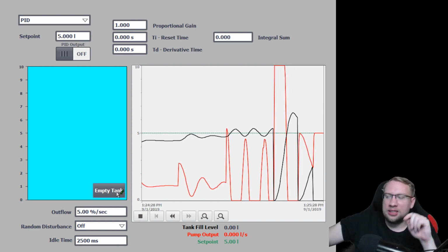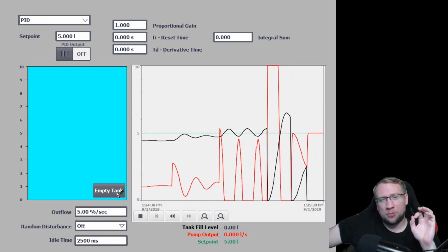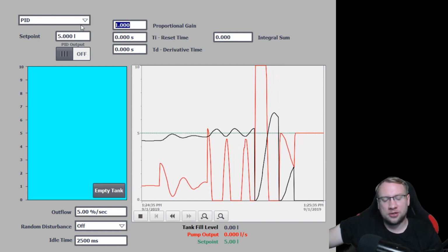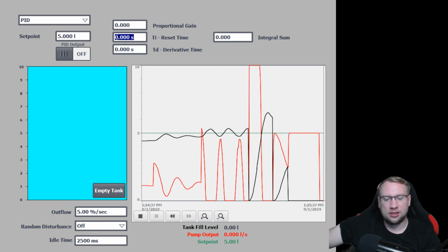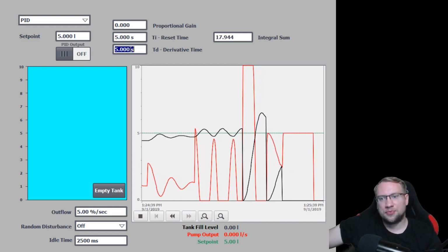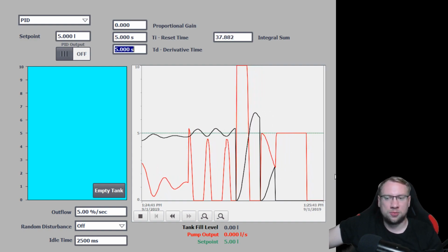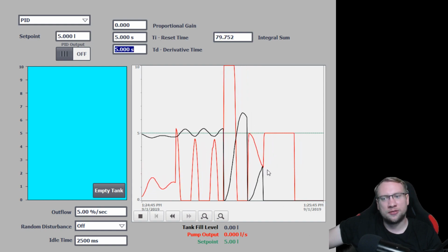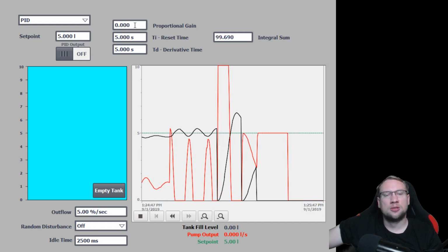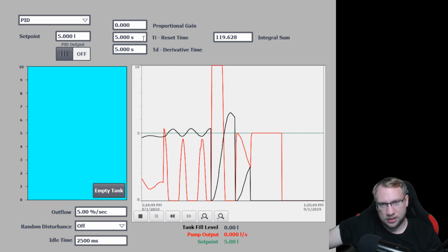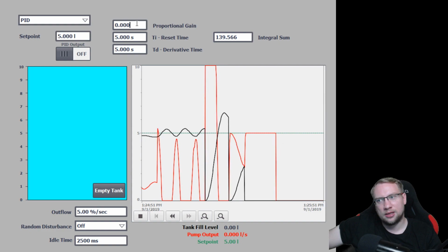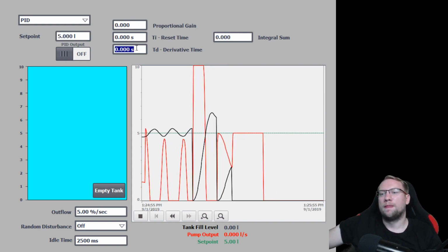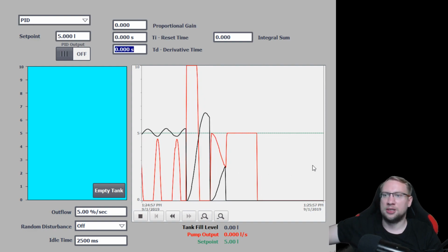Now, the Siemens PLC, the PID compact, works in such a way that we always need a proportional gain. If I do not have a proportional gain, the others will not affect my output. So my output, whatever is in the integral and in the derivative, multiplies with the proportional gain, right? So I always need a proportional gain. That's why it's good to have that at 1 or so. But let's see. See, I changed those and nothing happened here.